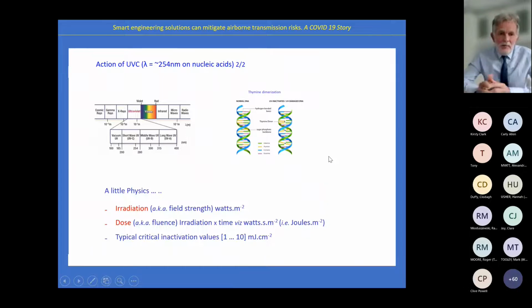Okay, a little bit of physics, not too much here. Light falling into our infected area will be irradiation. It has field strength, and we mentioned that we measure that in power per unit area. The dose of radiation delivered, the fluence, is this irradiation multiplied by the amount of time, and that gives us the unit of joules per meter squared. So it's not the irradiation per se, it's the radiation per area per unit time. The more time, the bigger the dose. The bigger the dose, the greater the inactivation potential. And in hand-waving terms, across the spectrum of microbes of interest within healthcare, we're attempting to deliver homogeneously between 1 and 10 millijoules per centimeter squared.